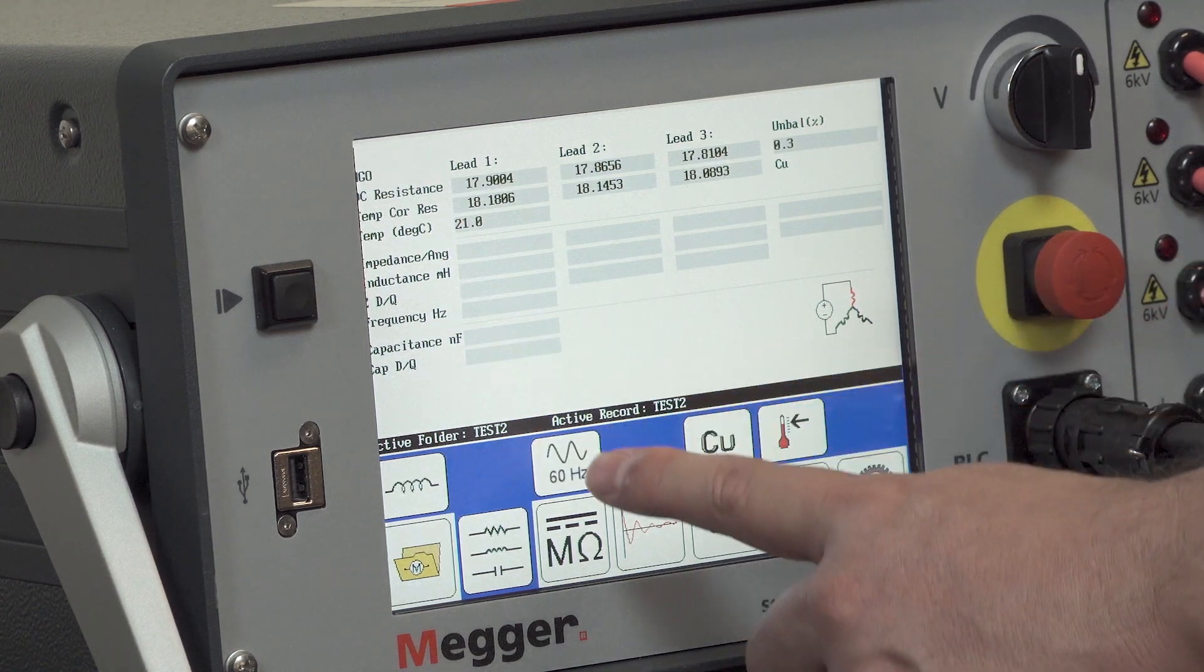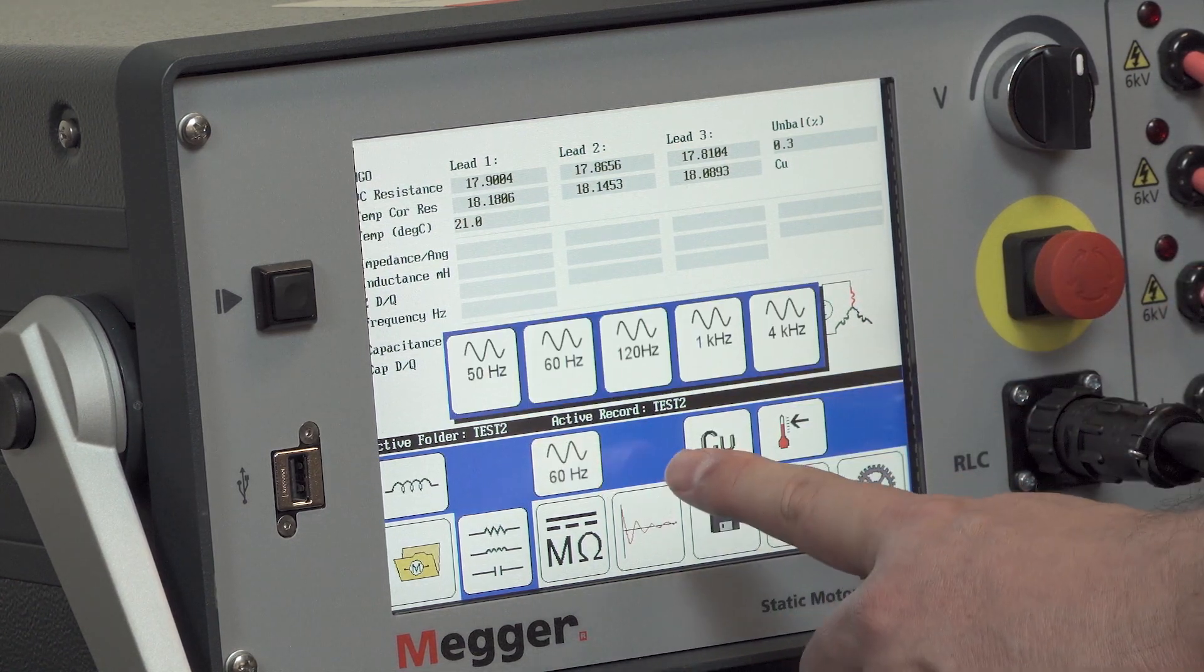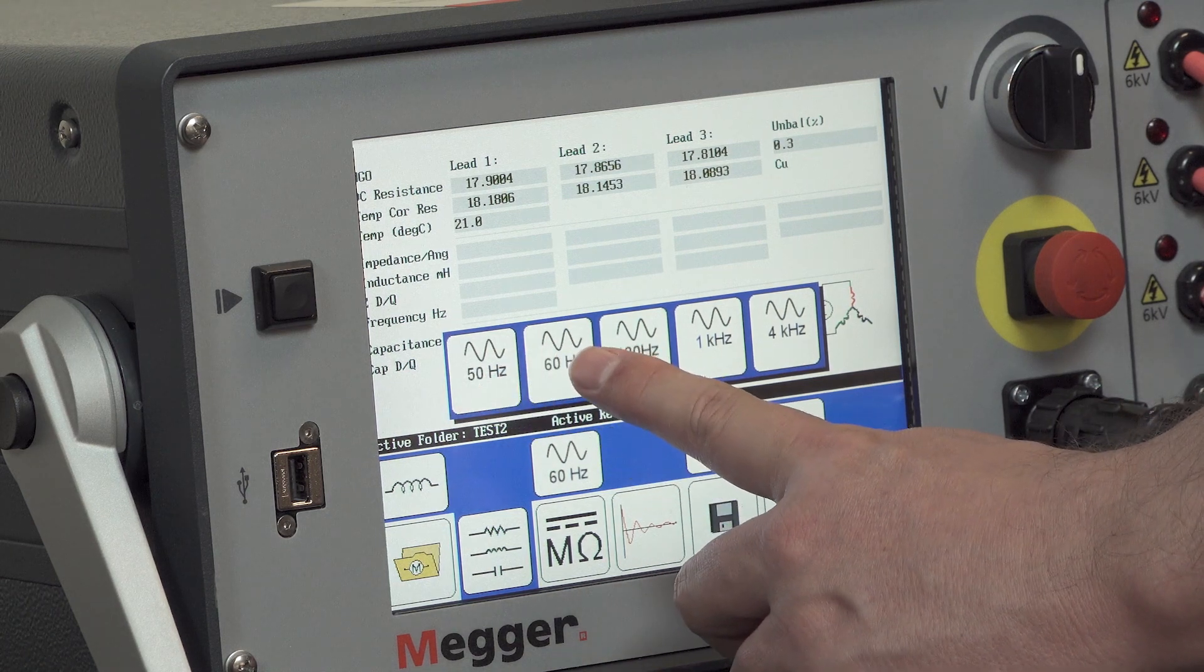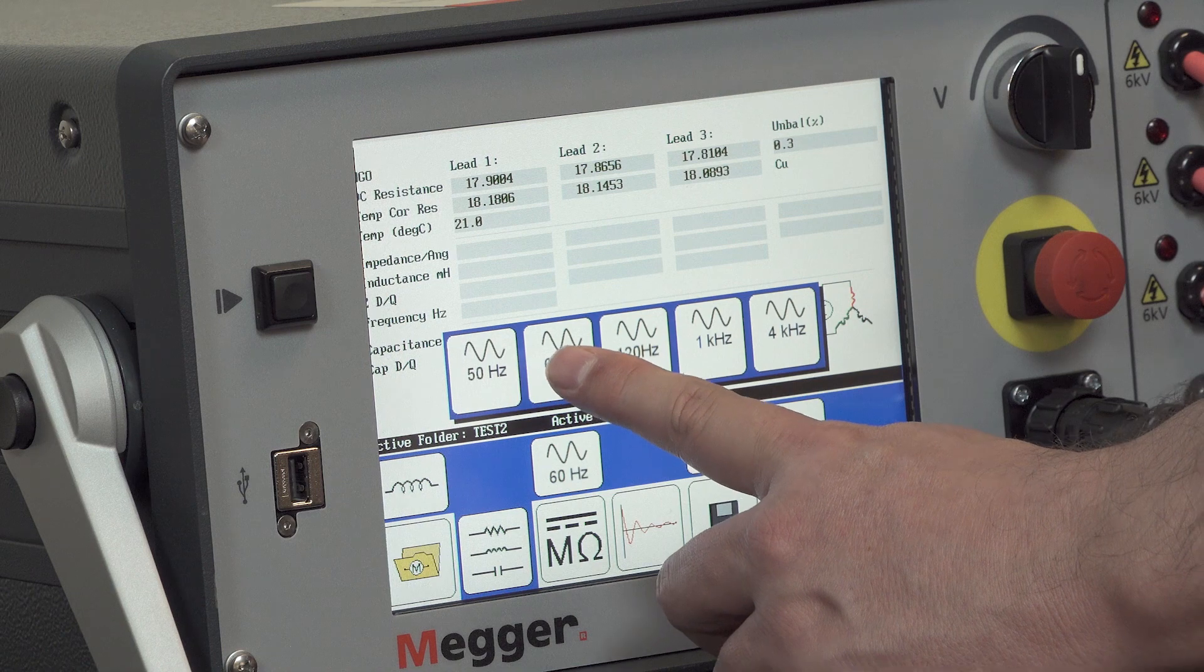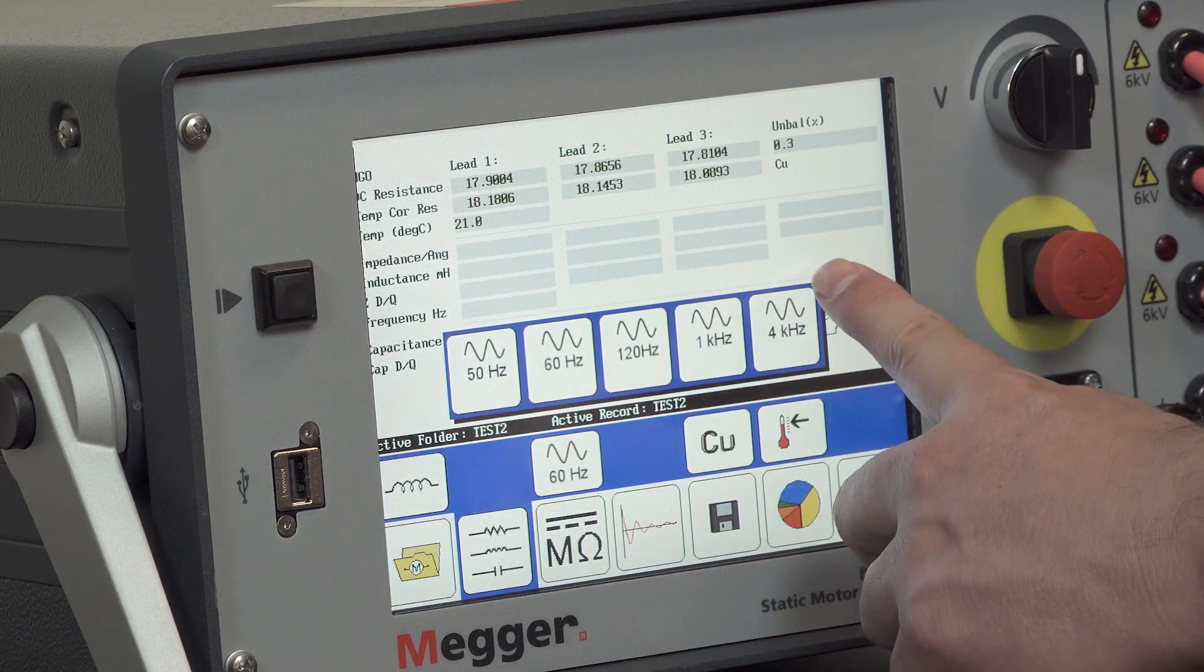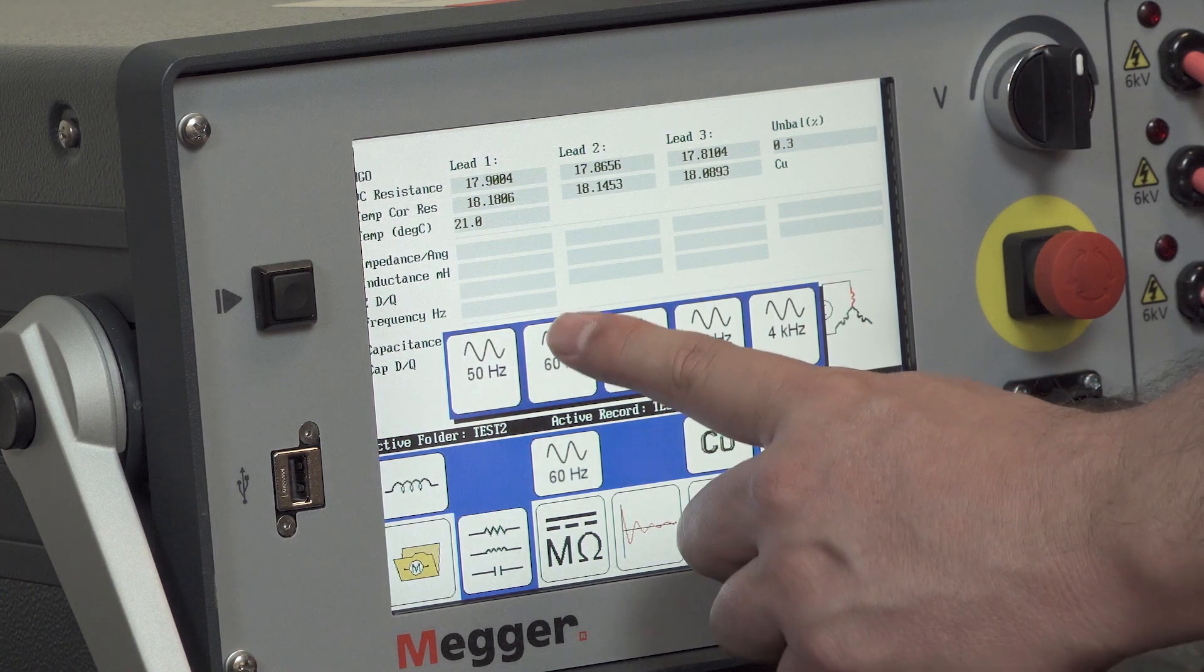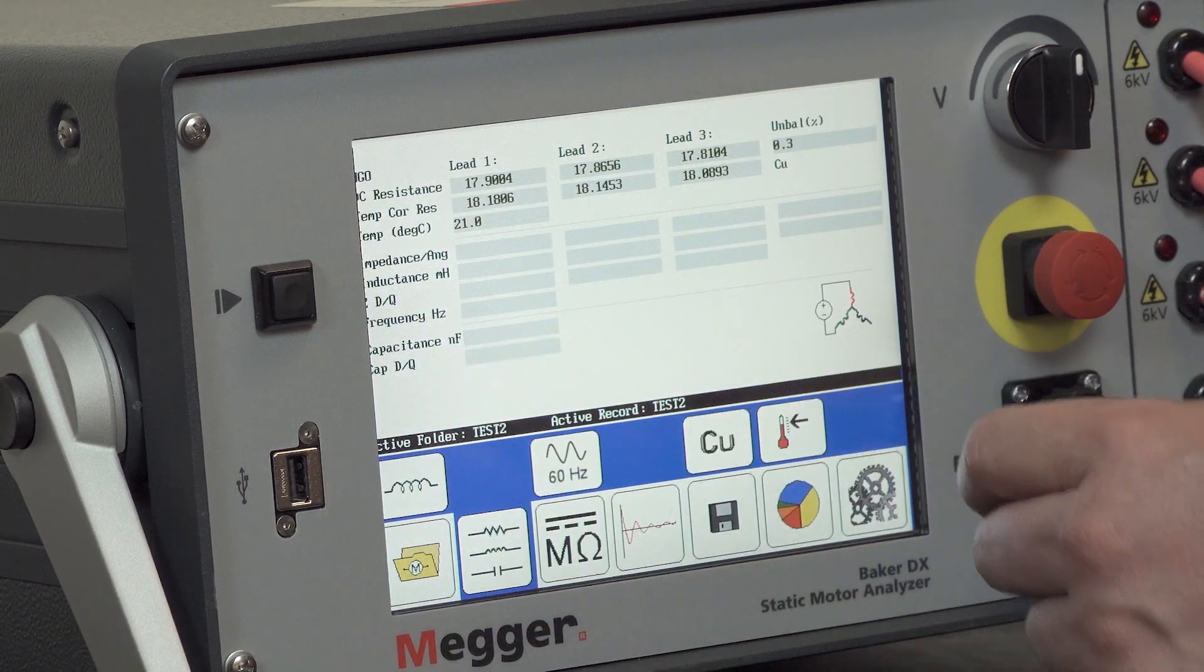We have an option to select frequency here. Typically we'll select the nameplate frequency of the device under test. There are higher frequency options for special cases. In this case I have a 60 Hz motor, I'm going to select 60 Hz.